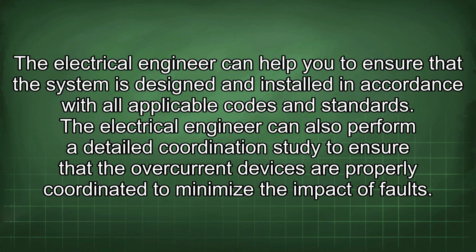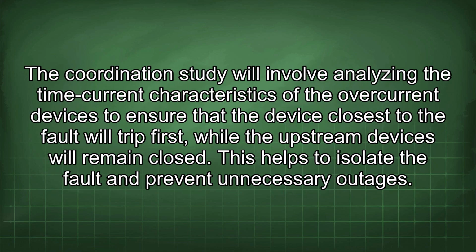The electrical engineer can also perform a detailed coordination study to ensure that the overcurrent devices are properly coordinated to minimize the impact of faults. The coordination study will involve analyzing the time current characteristics of the overcurrent devices to ensure that the device closest to the fault will trip first, while the upstream devices will remain closed. This helps to isolate the fault and prevent unnecessary outages.